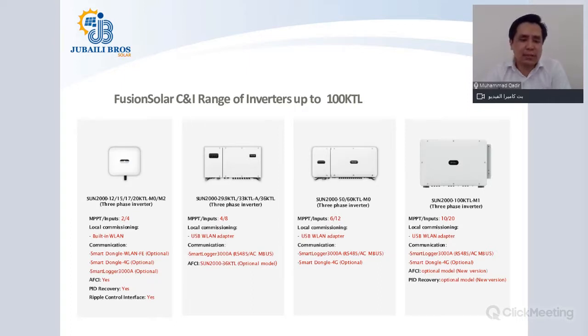Coming to the second class, which is SUN2000-36KTL for Middle East and Africa. This is a 4 MPPT inverter having 8 inputs. For the local commissioning, this inverter comes with USB WLAN adapter. This adapter is part of inverter package and is free of cost. And communication wise, for remote monitoring, you have the option of using a SmartLogger 3000A that can communicate via RS485 or AC MBUS. The AFCI, which is arc-fault circuit interruption feature, is an optional feature, and if you need that, you have to request.